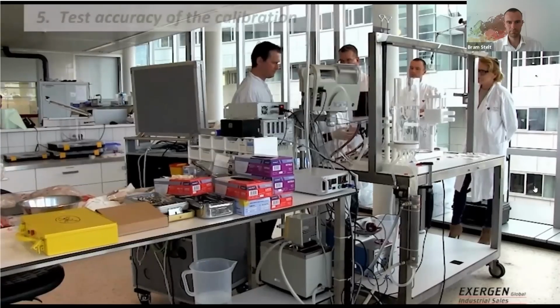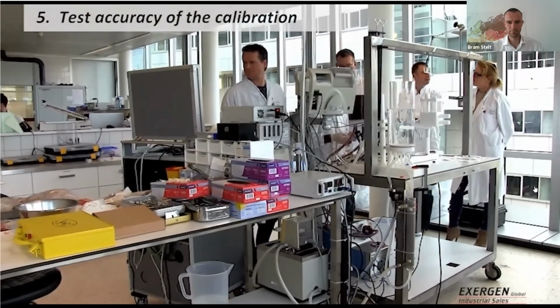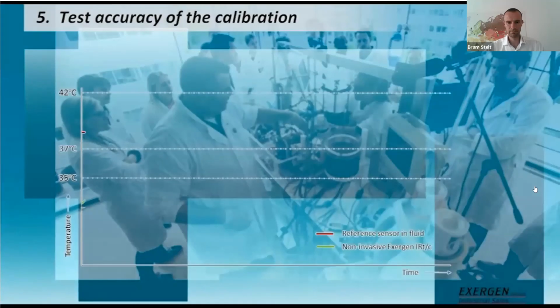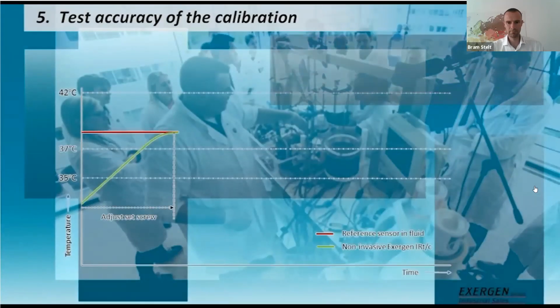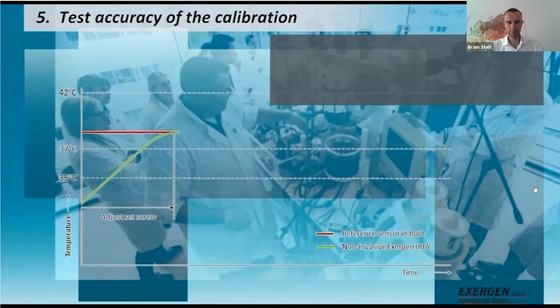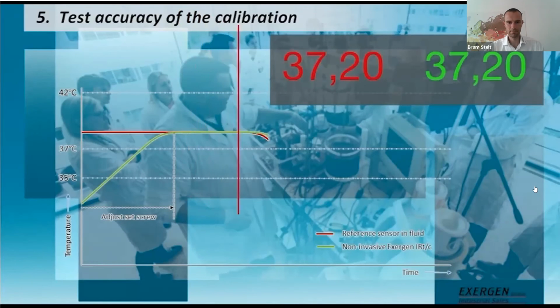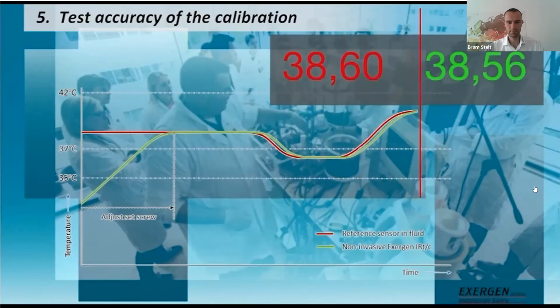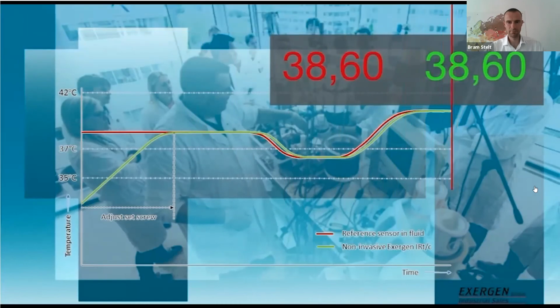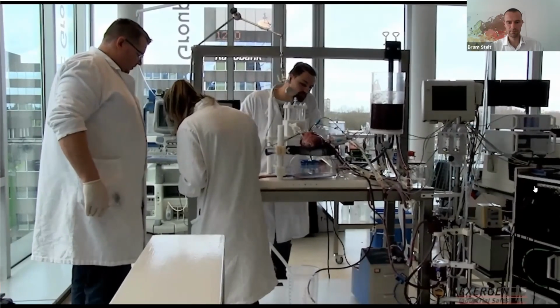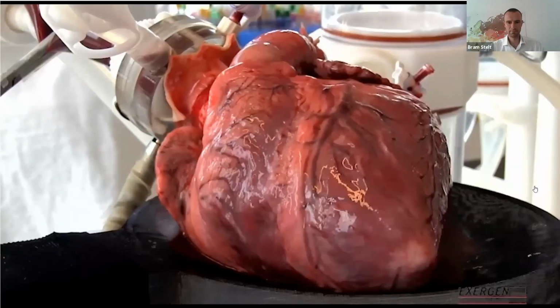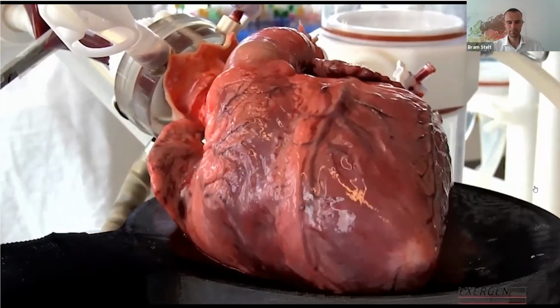Step 5. Test if the calibration is accurate over the internal temperature range of interest by varying the fluid temperature. In this case, between 35 and 42 degrees Celsius. If the sensor follows the reference sensor accurately, the calibration is successful. Possibly, some fine-tuning of the calibration screw is required to increase accuracy.